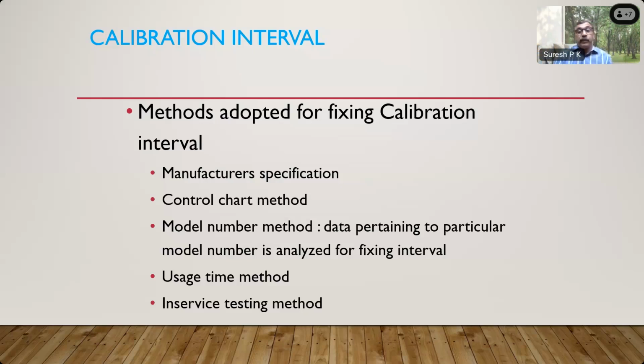Then you have the control chart method. Depending on the flow meter's performance, you make an inaccuracy chart and then find out at what interval it goes out of behavior. That is one method. Then the model number method: if data pertaining to a particular model is available with you, you can decide based on the model number. Then usage time, for how much time you are using it. If you are using it once in a year or so, you can do the calibration or verification once in 3 years or so. Then the in-service testing method: if you have an in-service verification method, you can do that. All these things are to be decided by the user. I am saying this apart from the law. If the law states that it has to be done once in a year, it has to be done once in a year. Otherwise, you are responsible for not doing it. So within the law, whatever is permitted can be done based on these methods.